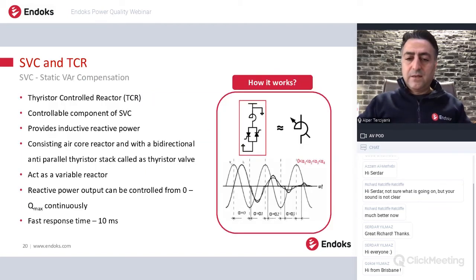And you see here another slide. Yes, the operating principle of the thyristor controlled reactor. You see, thyristors are very old but robust semiconductor devices. We can switch on thyristors whenever we want. So you see the waveforms. If we switch the thyristor at 90 degrees, the inductor current becomes purely sinusoidal and gives the maximum reactive power. But if we fire, or send the trigger signal to the thyristor, at 150 degrees, the current becomes very low, as you see here, and also not sinusoidal, because there are some regions where there is no current. So this is distorted, but the reactive power becomes lower.